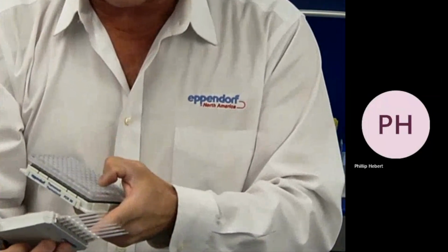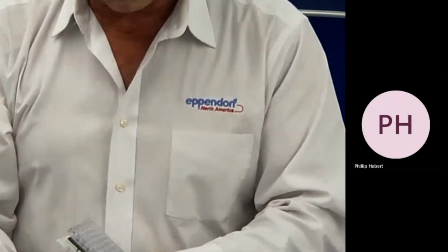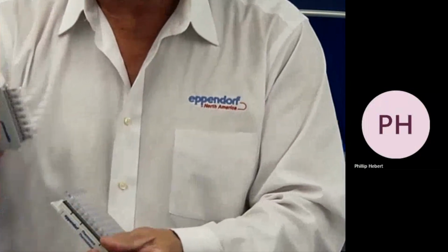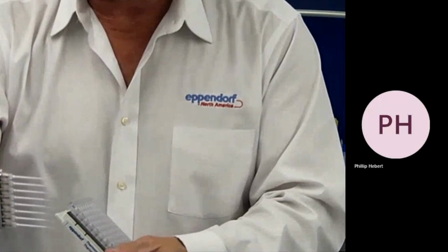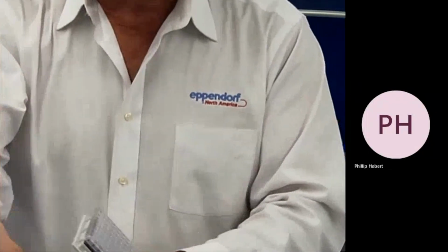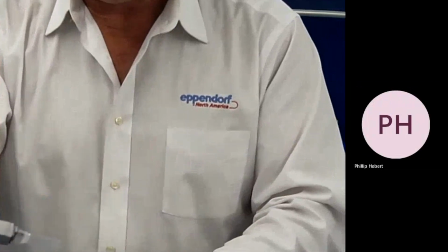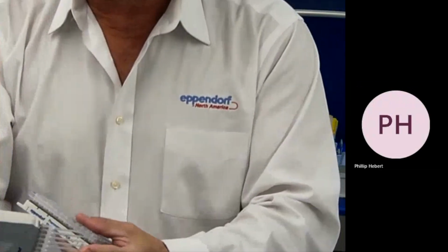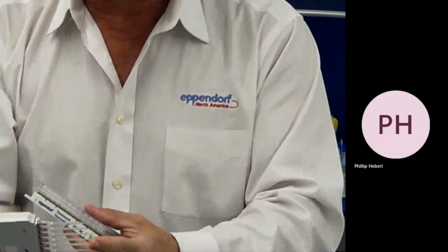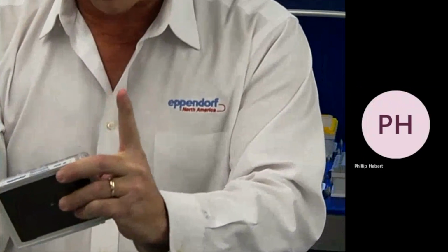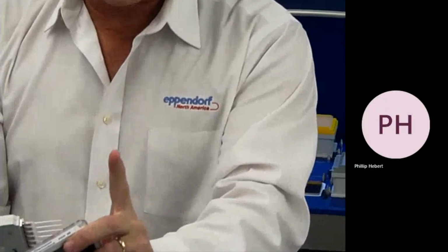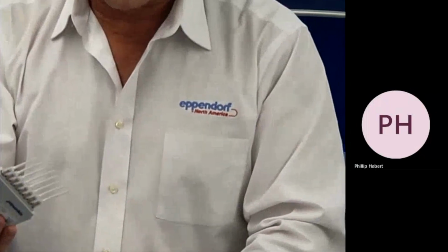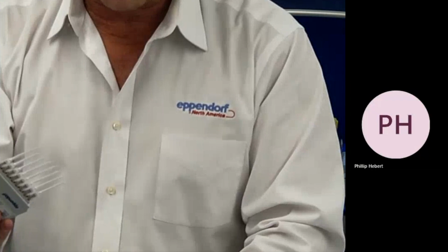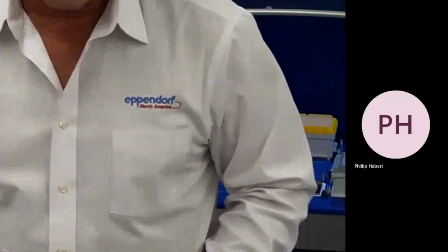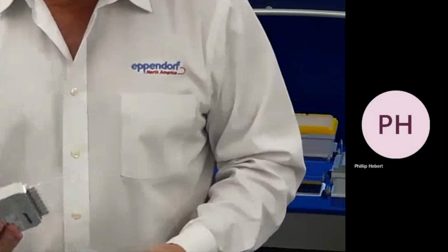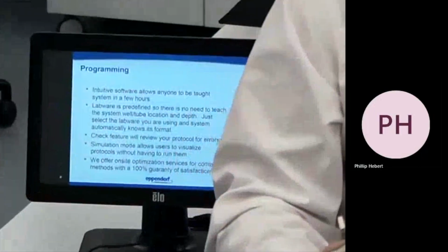And guess how many tips it takes. If you had just one tip that's a fraction of a millimeter further out, and then you go into a plate to remove all of the waste from the plate, that one is jutting out. Guess how many samples get pipetted properly out of that 96? One. Only one sample gets pipetted properly. All the others have residual ethanol left behind. So when you deal with a 96 channel head, you also have to deal with all the drawbacks of that.